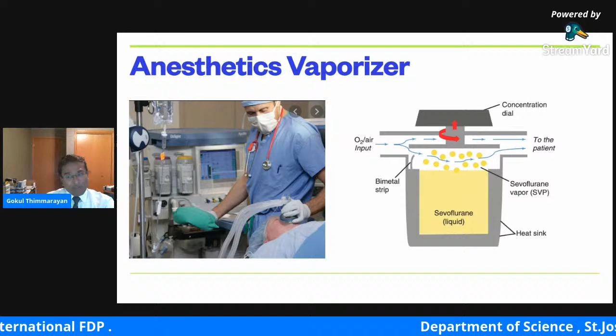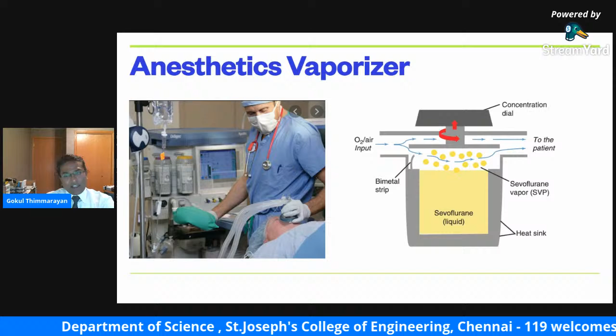So by titrating the amount of oxygen or air that passes through the vaporizer, we can titrate the amount of anesthetic agent that is carried along with the gas to reach the patient. In this process, the physics principles involved are vapor pressure, boiling point, and latent heat of vaporization. To stay in a state of equilibrium between the gaseous state and the liquid state, there are constantly molecules moving from either side. When the molecules in the gaseous state are carried away by the carrier gas, oxygen and air, again some more molecules get converted into the gaseous state, and it stays.